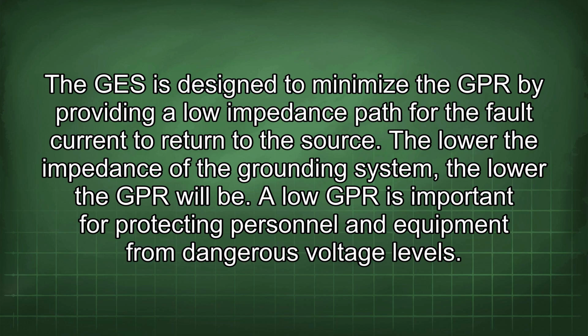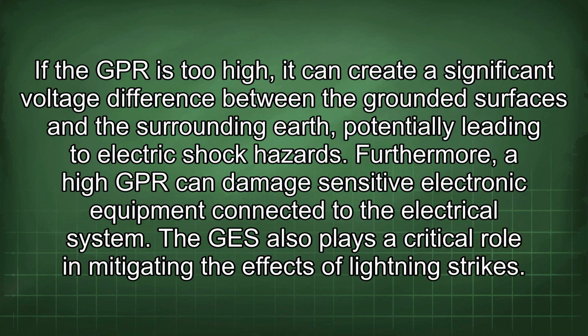A low GPR is important for protecting personnel and equipment from dangerous voltage levels. If the GPR is too high, it can create a significant voltage difference between the grounded surfaces and the surrounding earth, potentially leading to electric shock hazards. Furthermore, a high GPR can damage sensitive electronic equipment connected to the electrical system.